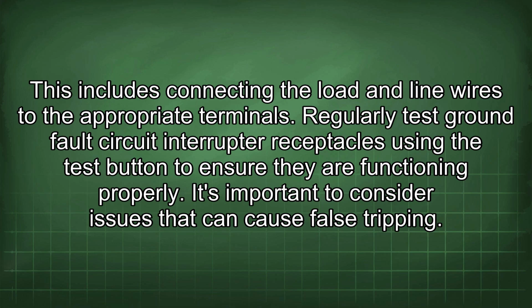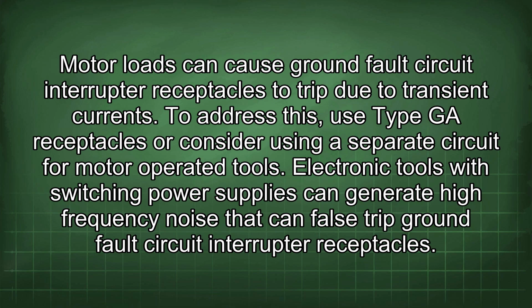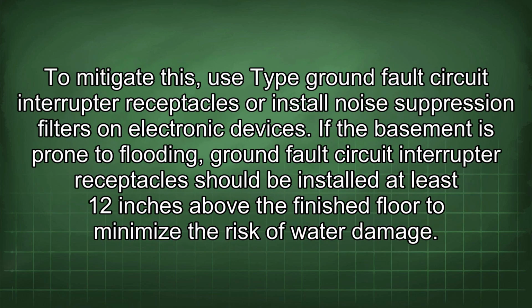It's important to consider issues that can cause false tripping. Motor loads can cause ground fault circuit interrupter receptacles to trip due to transient currents. To address this, use Type GA receptacles or consider using a separate circuit for motor-operated tools. Electronic tools with switching power supplies can generate high-frequency noise that can false trip ground fault circuit interrupter receptacles. To mitigate this, use Type ground fault circuit interrupter receptacles or install noise suppression filters on electronic devices.